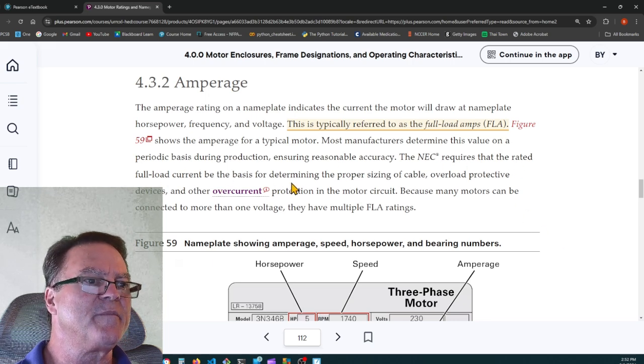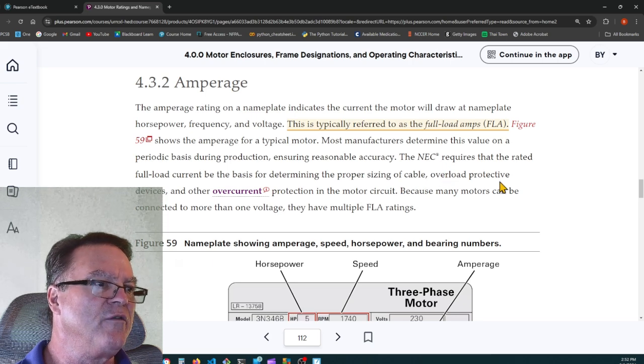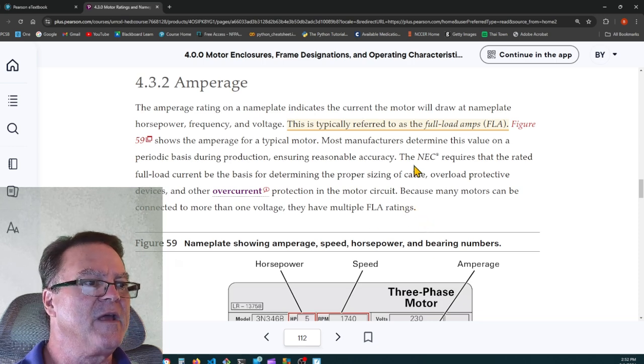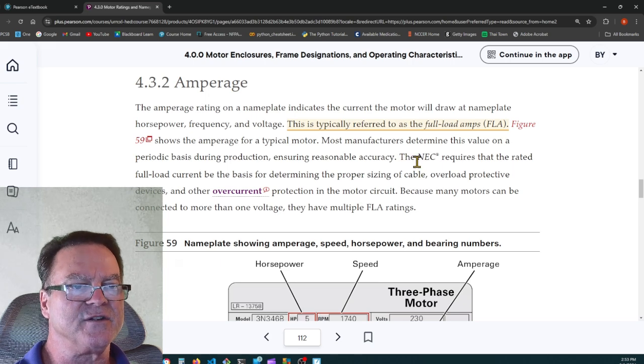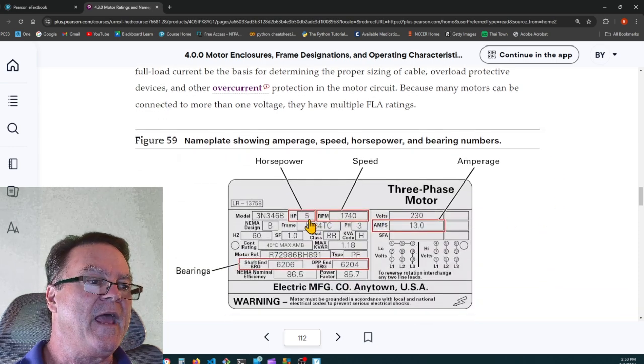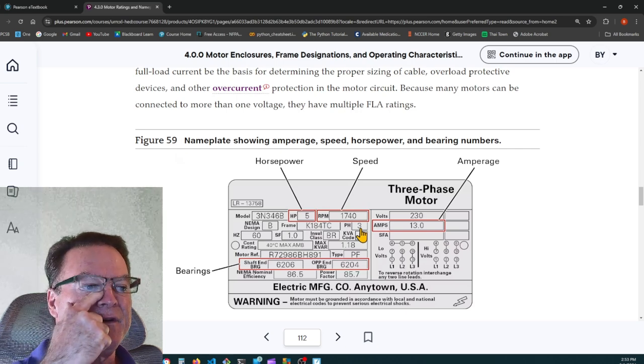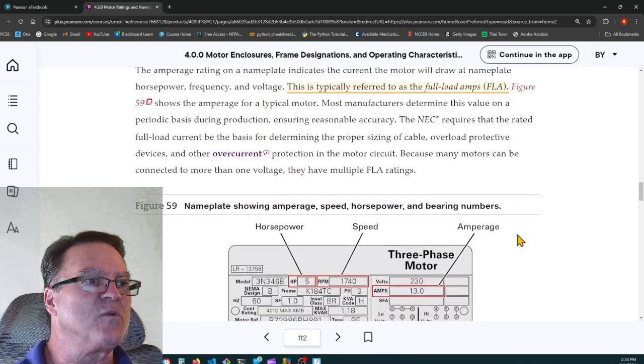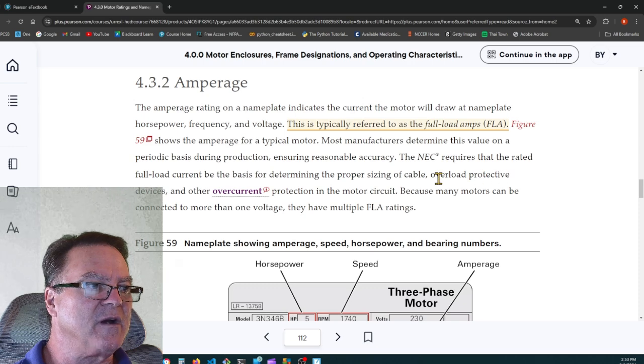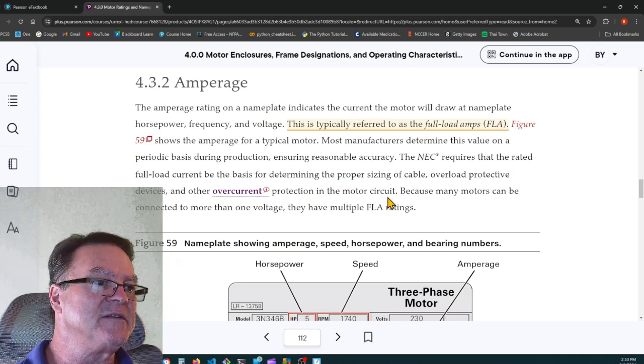The NEC requires that the rated full load current be the basis for determining the proper sizing of cable, overload protection devices, and other overcurrent protection in the motor circuit. Because many motors can be connected to more than one voltage, they have multiple full load amperage ratings. National Electrical Code is going to tell us for standard motors, we're going to use tables 430.247, 248, 249, and 250 to determine the full load amperage of that motor going by horsepower and voltage. If it's a three-phase, 5 horsepower motor, we'll go to 430.250, and we'll look to see what the amperage rating is. And that's what we'll use to size the cable, the overload, the overcurrent protection, any disconnecting means.